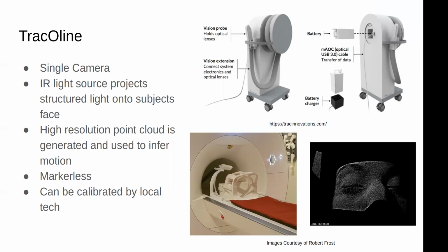Not to go on a side thing, but in terms of just plain EPI, and this is something maybe you guys at Martinos have the capability to do, that reference scan, at least on Siemens, is so critical that acquiring a couple of them and picking the best one, the one where the participant didn't move, seems to me one of the easiest ways to improve motion sensitivity in your scan. Otherwise you're relying on that one reference scan at the beginning of the run, and if they happen to swallow or move their eyes or wiggle, then you're in trouble if you're not watching your real-time reconstruction.